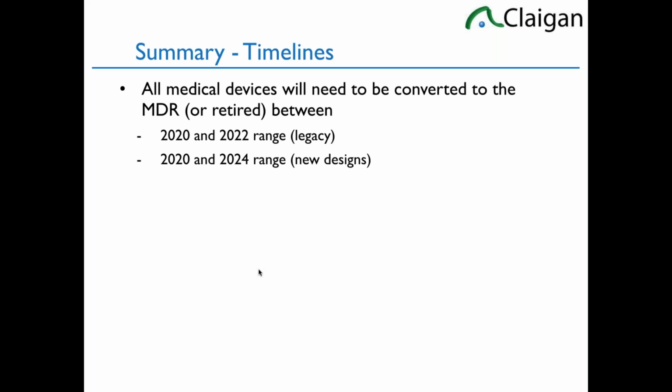So you'll often have compliance deadlines for legacy, pre-2017 products between 2020 and 2022. And anything you qualify from now to the start of MDR, you'll have to recertify to MDR somewhere between 2020 and 2024. So you can have a variety of compliance deadlines for a variety of products. It's going to make the project a little more complicated. It's going to make reporting to management more complicated. It's not like how many are compliant by this specific deadline. It's scattered over a wider range, especially for legacy products. On the bright side, your workload can be more evenly spaced. It doesn't have this one spike at one deadline. You'll be able to spread them out a little more, which may work effectively. But the communication to management may be more difficult with the scattered compliance deadlines.